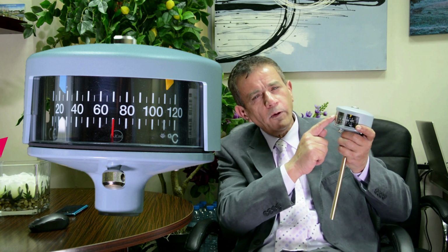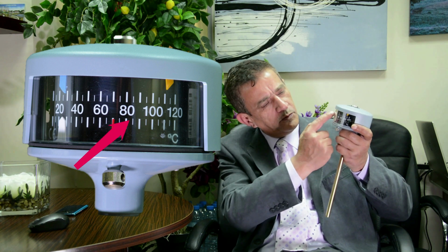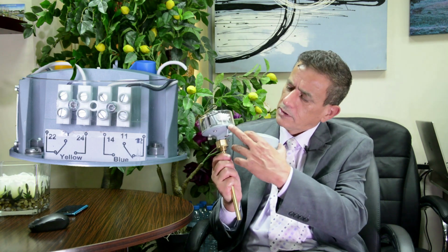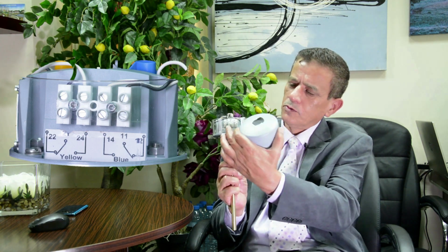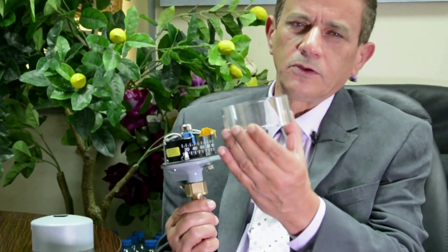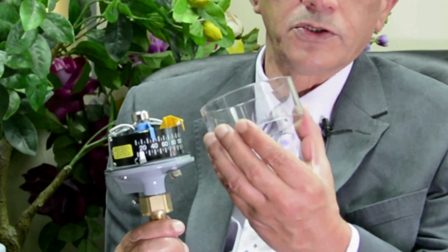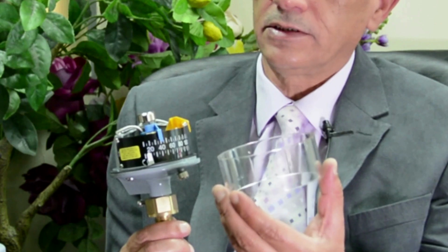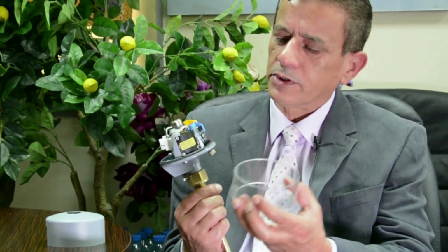If with contacts, as we can see, there are blue and yellow points on top for minimum and maximum temperature. These will be connected to a micro switch. See here, there are yellow and blue wires coming here to use them for tripping the circuit breaker or giving an alarm or whatever. And this is the window. It's made of polycarbonate. It's UV stabilized in order not to get yellowish with time.